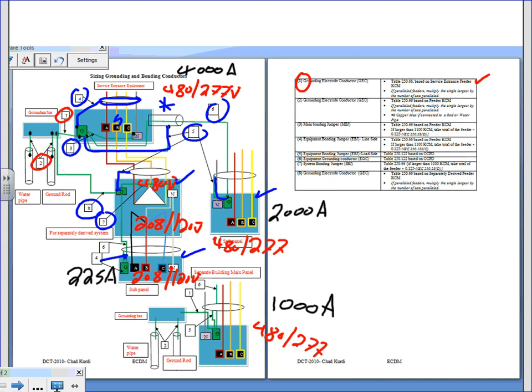Okay, so I need to size everything for this system. I have a 4,000 amp switchgear feeding a 2,000 amp panel and a 1,000 amp panel, and also feeding through a transformer, 208/120, a 225 amp panel. And I need to size all these eight things. I want to remind you guys, when we go to a separate building, look how we have to create the same thing. You have to create a grounding bar here, and you have to tie to every grounding electrode system in the second building, exactly like in the service. See how this one looks exactly like this in the second building.